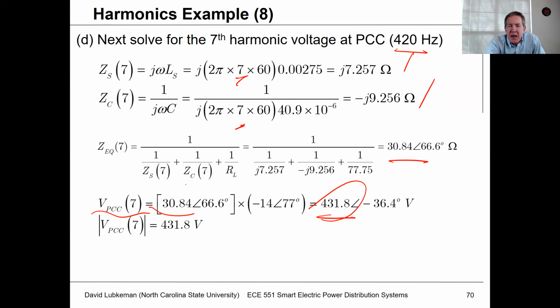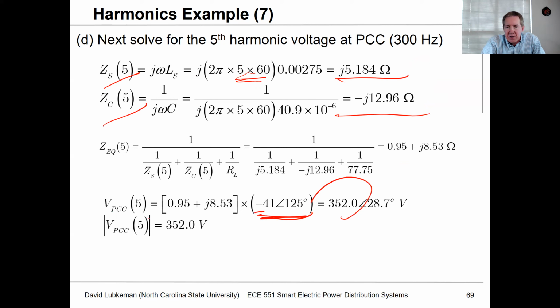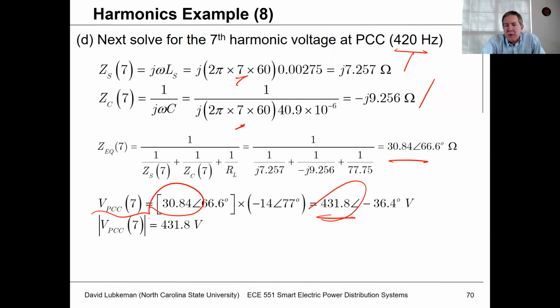because what's going on is I'm hitting a resonant point. The net impedance is actually going up in this case. All right, so this is the thing you have to watch out for: this value becoming large. Because even if you have a smaller harmonic current, you can still have a lot of harmonic voltage if the impedance goes up. And so what we're seeing is this sort of effect right here, where this is actually closer in frequency to the 7th than it is to the 5th harmonic.